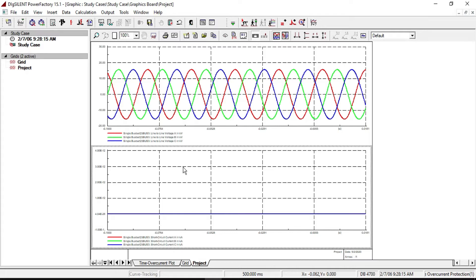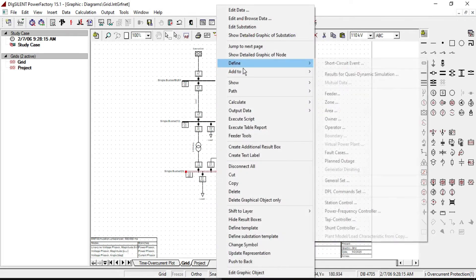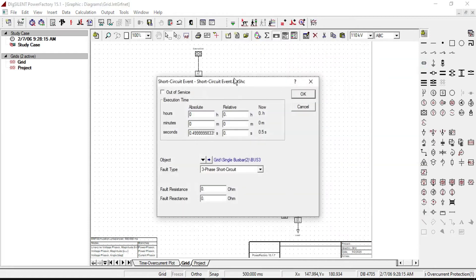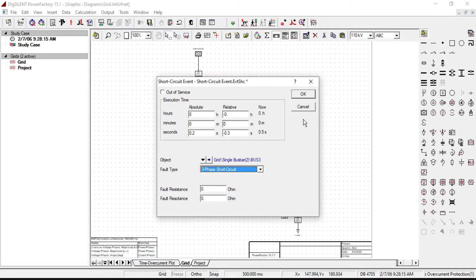To evaluate the short circuit current for different scenarios, we need to define short circuit events. Go to the line diagram of our network system. Right click on bus 3, from Define click on Short Circuit Event, and a new short circuit dialog will pop up. Assume from 0 to 0.2 seconds there is no fault, so enter 0.2 seconds for the execution time of the fault. Fault type is three-phase short circuit. Click OK.